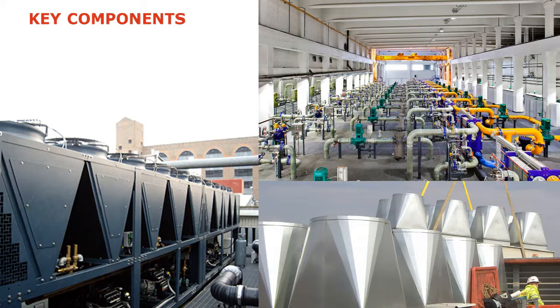And certainly what we've also seen is, particularly in Amsterdam, they use aquifers as a means of helping that system. They're boring a well that's in cold water, taking that cold water and passing it through and depositing it back in a hot well. Then through the winter months, they're taking the hot well, passing it back through to maintain the temperatures we're expecting, cooling it down and putting it back in the well.